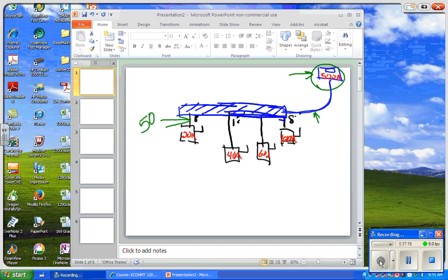Okay, now let's look over here. We've got a 100 amp load, possibly. We've got 100 amp fuses in here anyway. Can we go with a 50 amp wire? Depends on the load. Let's say it's an 80 amp load. The load is 80 amps, not the fuses. The fuses are in a 100 amp disconnect. We can put an 80 amp fuse in it, right? Or we might need to put a 100 amp fuse on it and use 100 amp wire for an 80 amp load because, well, we'll get into that later. That's next week.